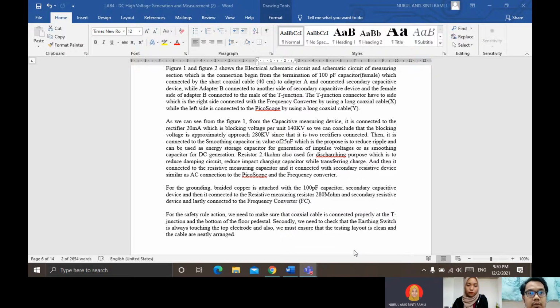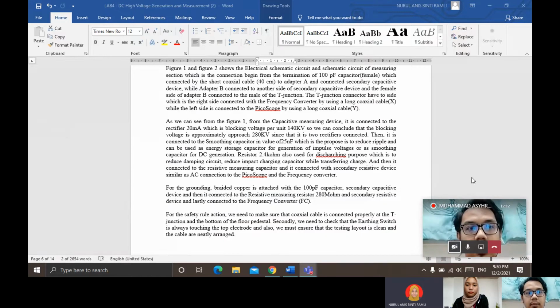From the capacitive measuring device, it is connected to the rectifier rated 20 mA, whose function is blocking voltage, at 140 kV per unit. So we can conclude that the blocking voltage approaches 280 kV, as two rectifiers are connected.